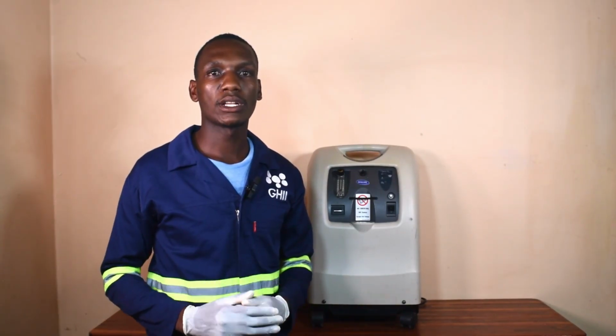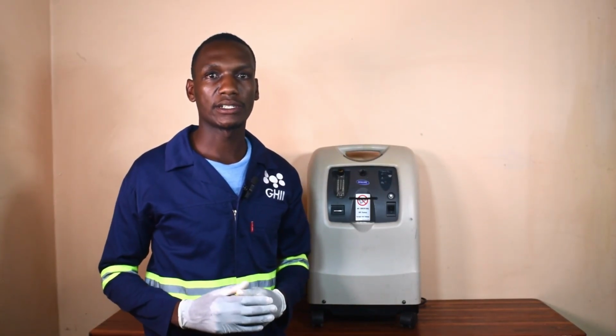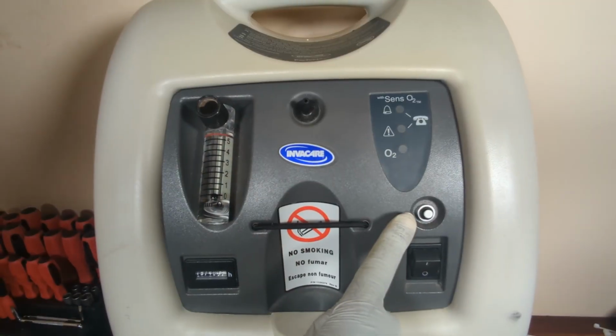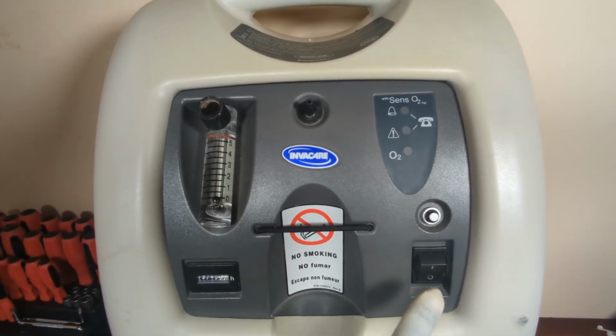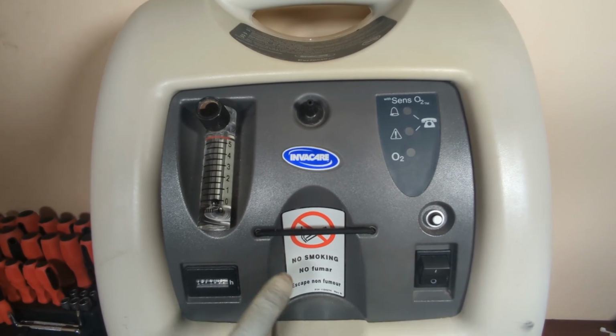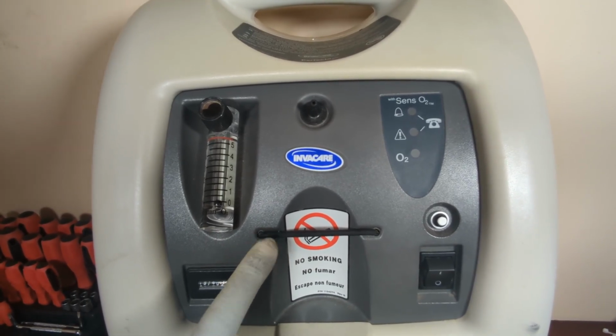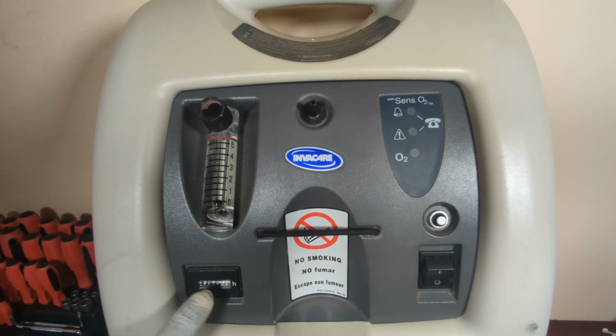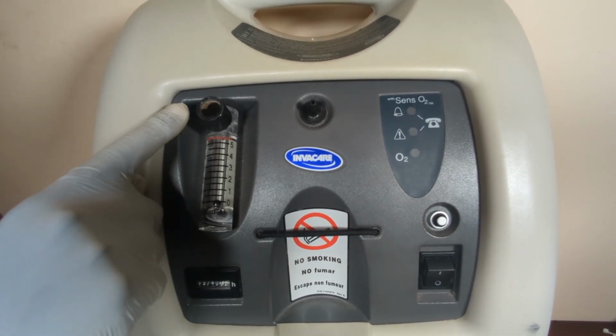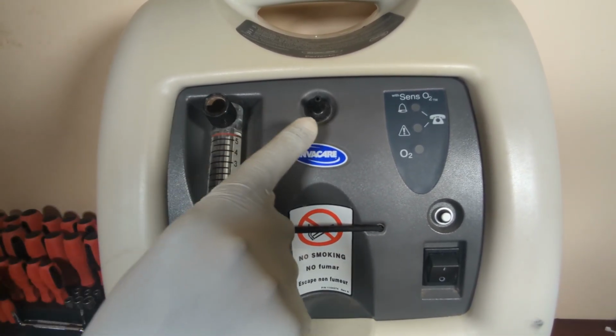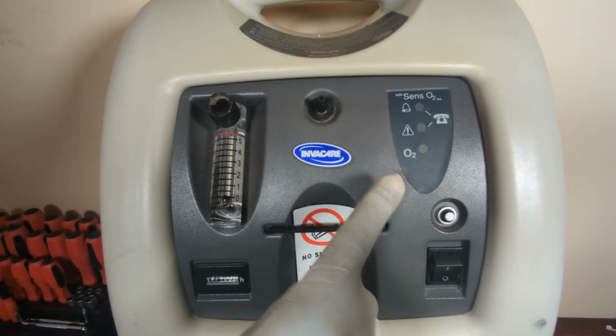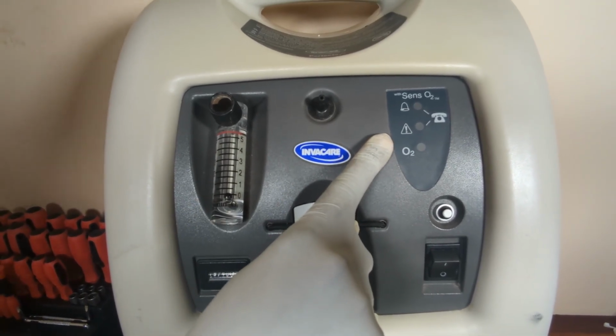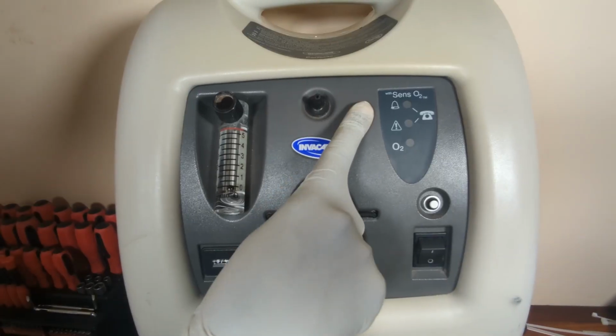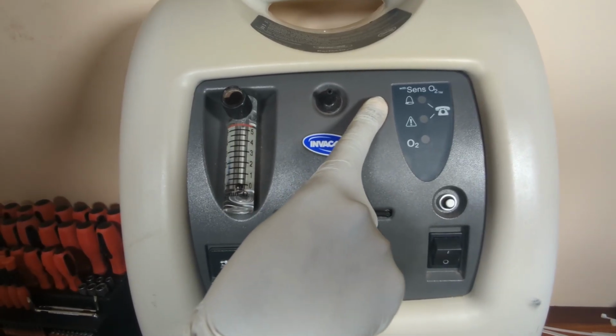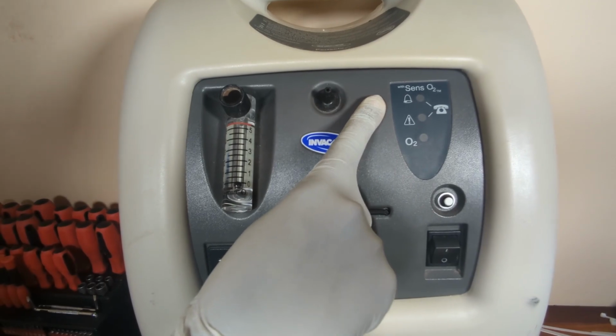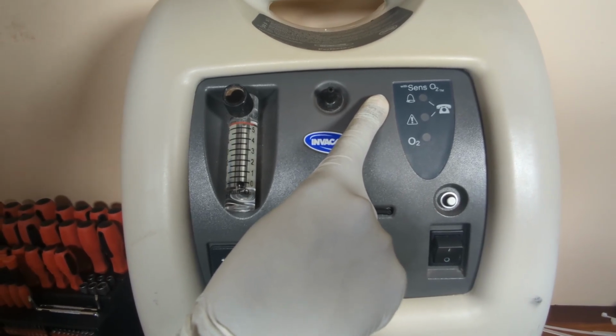Now, let us look at the external parts for this oxygen concentrator. Here we have circuit breaker reset button, power switch, humidifier bottle holder, hour meter, flow meter adjustment knob, oxygen outlet port, and finally the indicator lights panel. This panel consists of LEDs that indicate the status about the machine's performance and other issues.